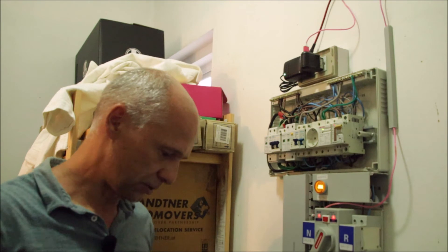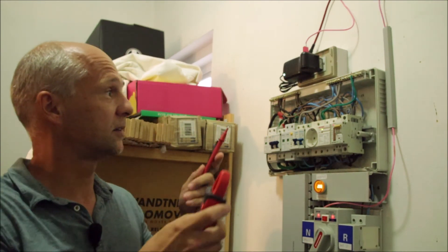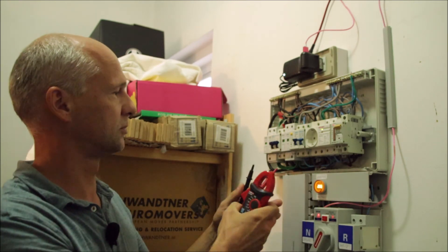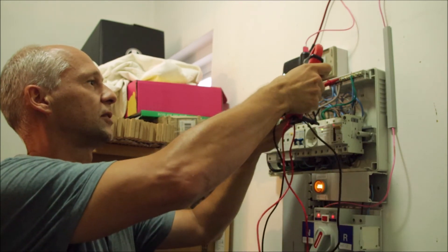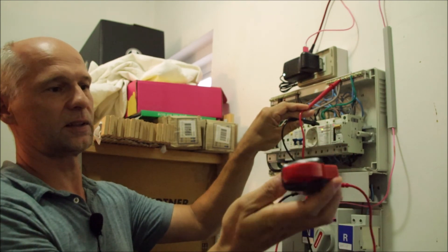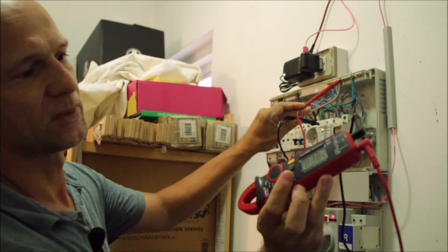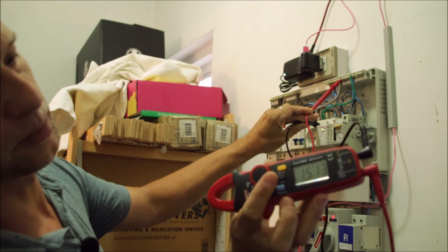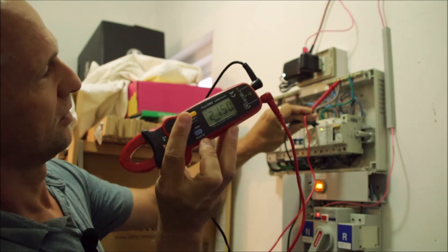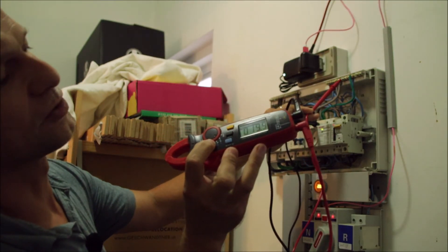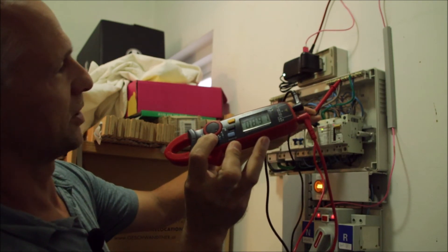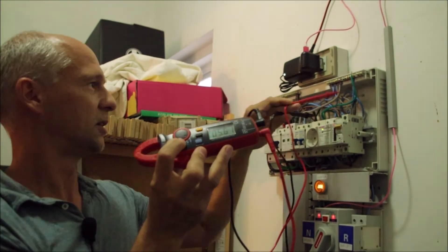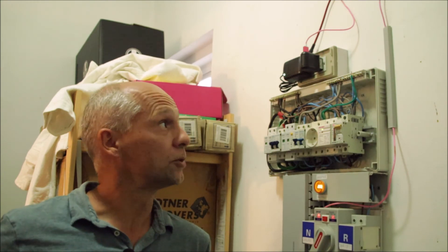And we are going to measure the voltage between neutral and a point of earth. So here I have the point of earth and here I have neutral potential. And as you can see now at the moment I have like 12, 13, 15, 17 volts. So there is potential on the neutral. It's rising slightly so now we are 20. This can vary from inverter to inverter and from time to time. So when we did that last time we had almost 50 volts on the neutral.